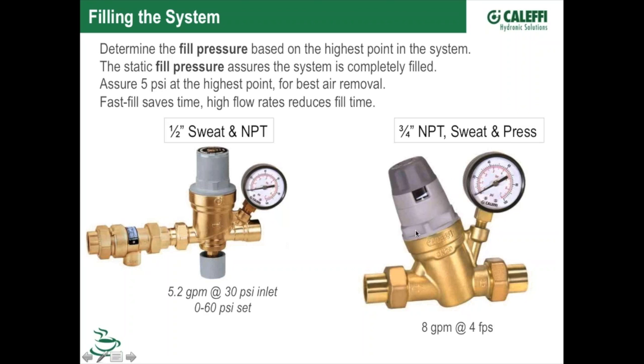Over here we're showing a similar valve here. This is a 3/4 version, so a little bit higher flow rate. We'll get about 8 gallons per minute through this device with a velocity of about 4 feet per second. Same dial up here that you can dial in and adjust the pressure on it, the gauge again to confirm it and stuff like that. Unique about this one, going back to this for a second, it does go up to 60 psi. A lot of the other brands that you might find out there typically will end at 30 or 45 pound pressure. So if you have an application where you need the higher fill pressure, it's built right into that valve.